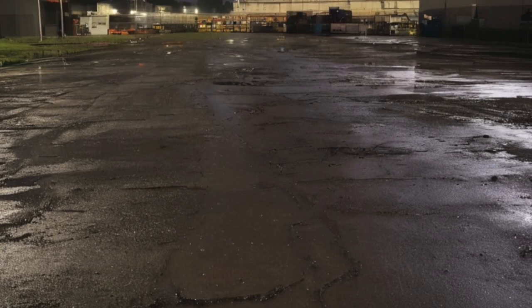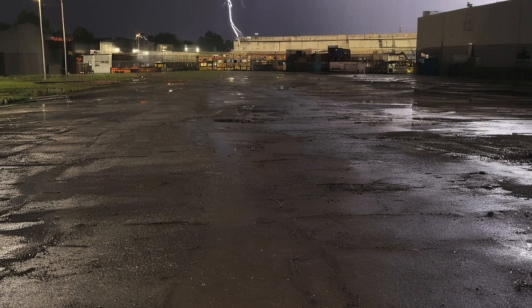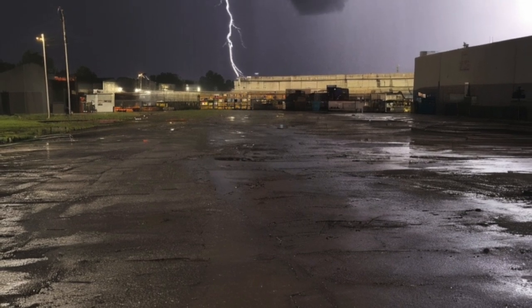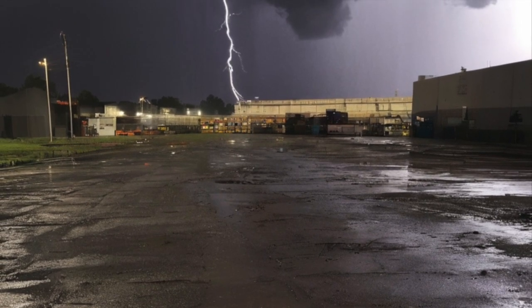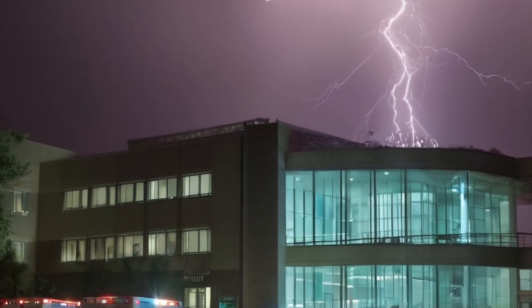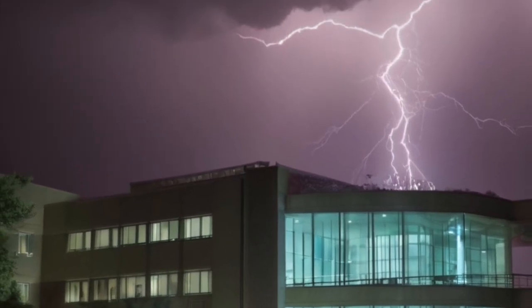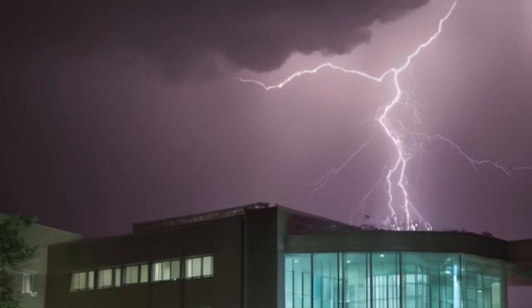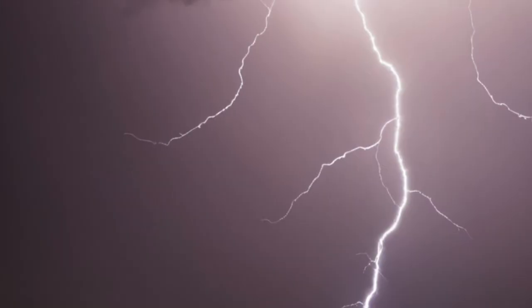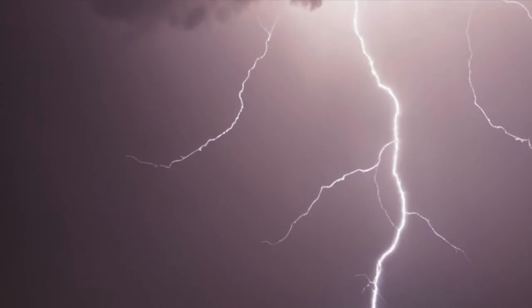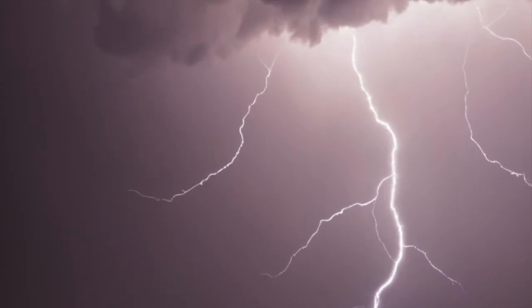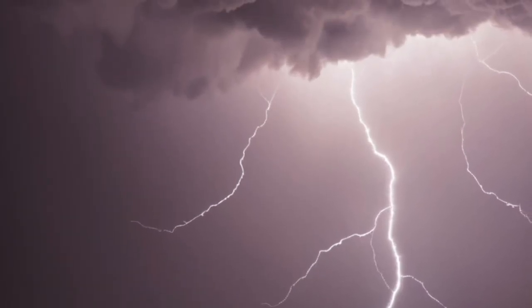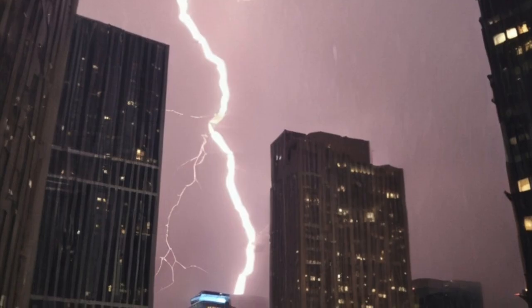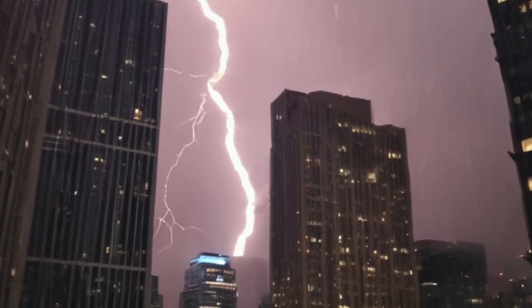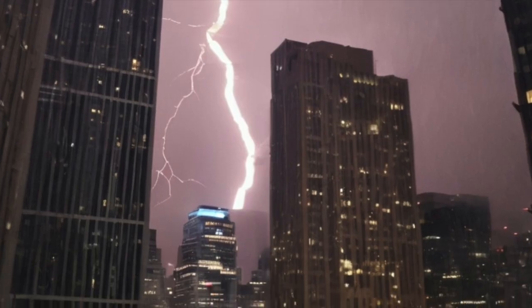This early calm exists because modern high-rises are built to guide lightning safely into the ground. The tallest structures bristle with metal rods called air terminals, forming the top layer of a lightning protection system designed to intercept strikes. When a lightning bolt connects with one of these terminals, the electrical charge flows through heavy copper or aluminum conductors that run inside the walls. These conductors channel the energy into deep grounding electrodes buried far below street level.